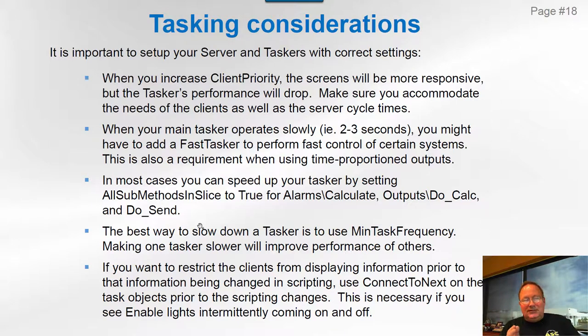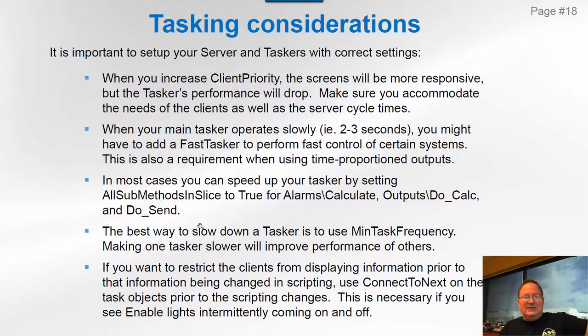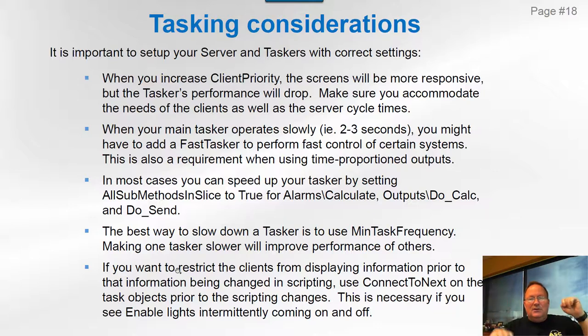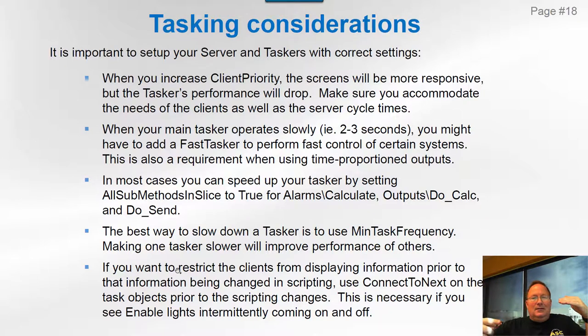To speed up the client or other quicker taskers, you can incorporate a minimum task frequency to slow down or regulate taskers you don't need operating too quickly. If a tasker is running at half a second and you're fine with two seconds, use minimum task frequency to slow things down. If you want to restrict clients from grabbing information between the operation of certain tasks, use 'connect to next' on those tasks. Don't use connect to next on all tasks, because that's basically the same as telling it to do all tasks in one slice — but you can connect tasks one, two, and three together so you're not updating the screen with incorrect information.